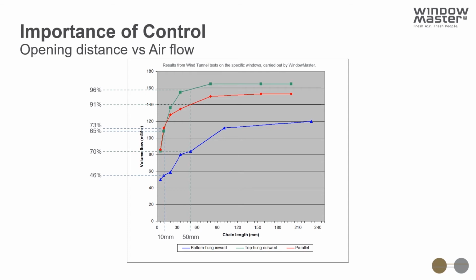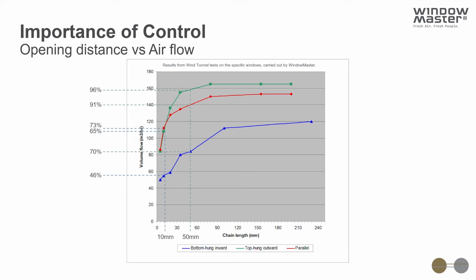However, in a typical cross ventilation situation, such as this, where it's balanced cross ventilation, when you open the vents, the pressure differences either side of the vent actually create a much higher proportional flow of air at relatively small openings. So you can see that at only 10 millimeters of opening, you can achieve approximately 60% of the airflow through the open window. The importance of this is that when we're tracking the change in demand for ventilation in the space, we need to understand relatively small openings of the windows can deliver relatively high volumes of airflow, and therefore it's critical that we have the ability through the control system and the actuators being used to be able to open the vents to very acute and small openings according to the ventilation demand and the weather conditions outside.